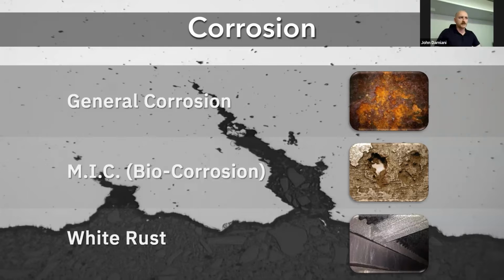General corrosion is basically the idea that water plus metal always results in corrosion. With any water treatment program, we're really just working to minimize that, not completely eliminate it, since it's impossible to eliminate all forms of corrosion. What we're trying to do is implement a program that extends the life of equipment to where it's within or exceeds the expected lifespan, avoiding premature failure from excessive corrosion.